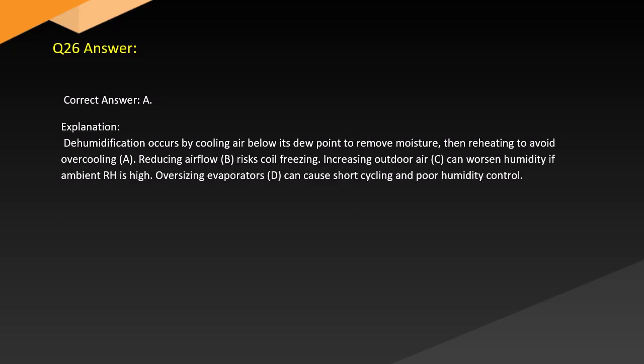Answer. Correct answer: A. Explanation. Dehumidification occurs by cooling air below its dew point to remove moisture, then reheating to avoid overcooling. B. Reducing airflow risks coil freezing. C. Increasing outdoor air can worsen humidity if ambient humidity is high. D. Oversizing evaporators can cause short cycling and poor humidity control.